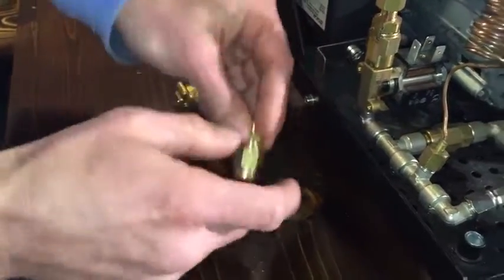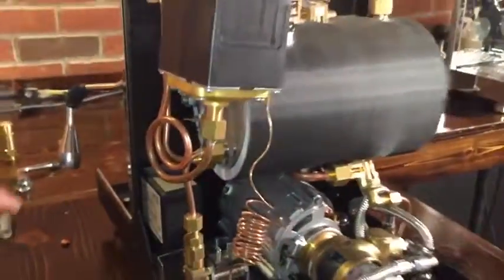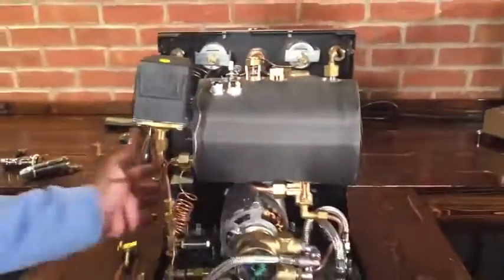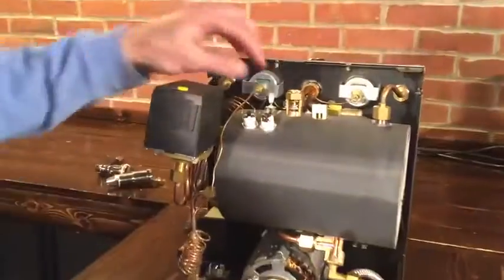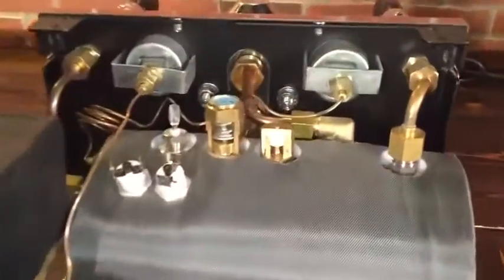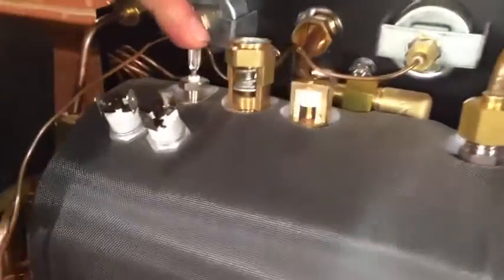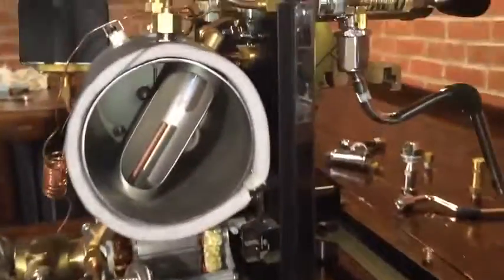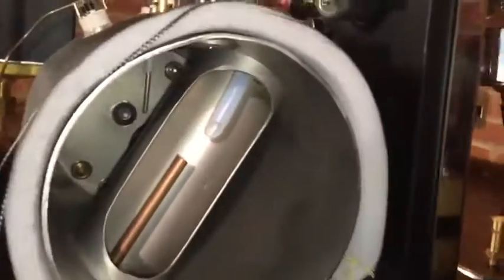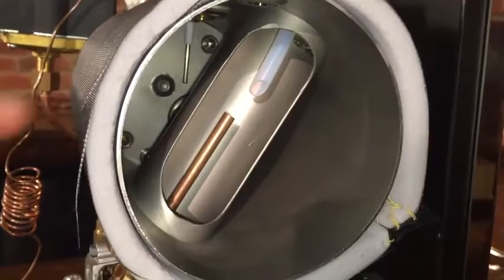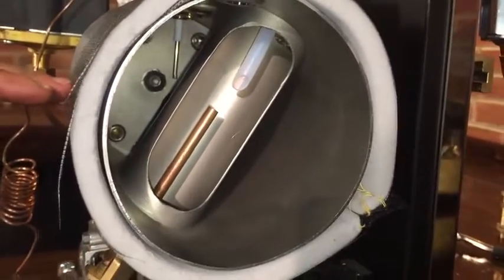Once we get through this check valve, we go directly into the boiler and it fills it up. I'll stick with that for a minute - the boiler level is controlled through this probe here. There's normally a wire that goes to that - see it deep inside, the little stick sticking down there. So the water level is approximately there.